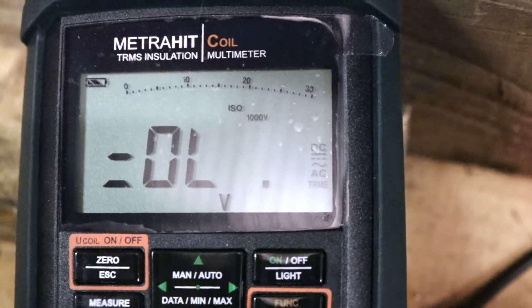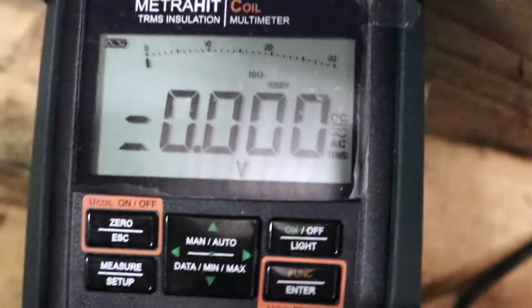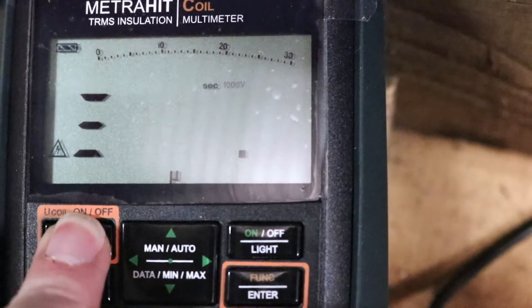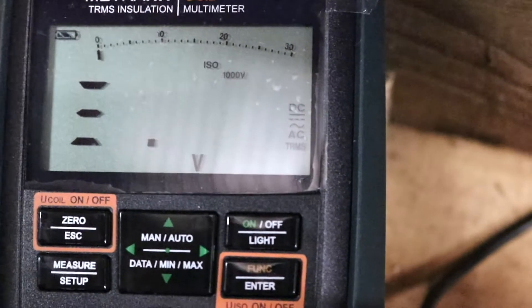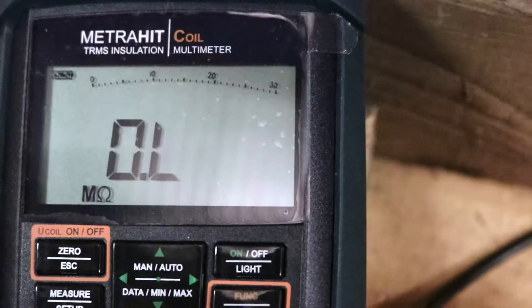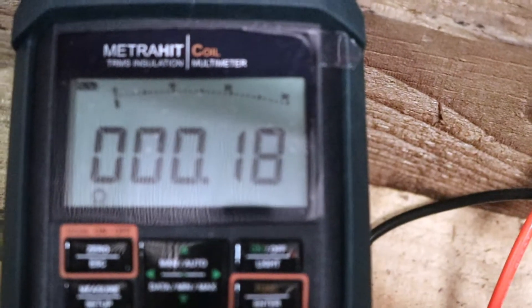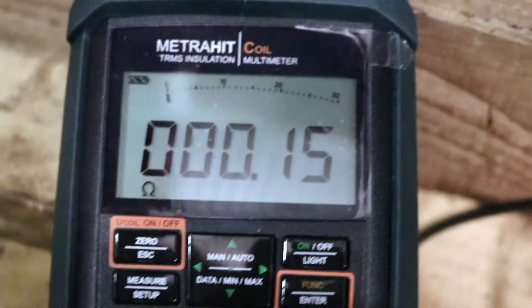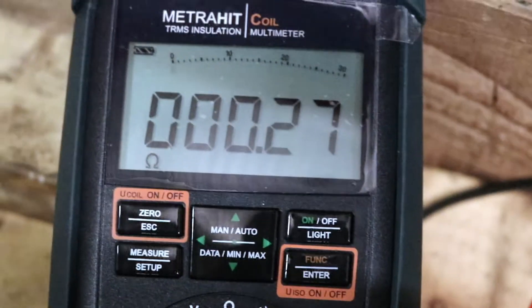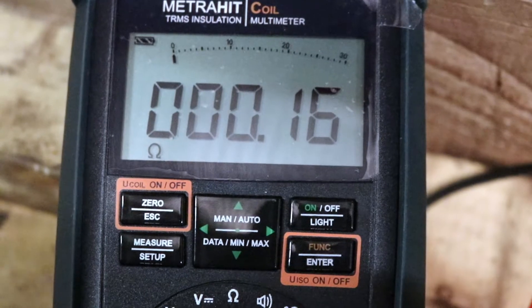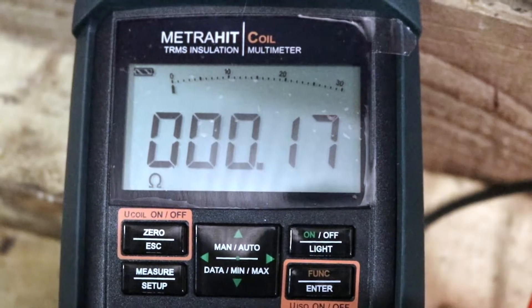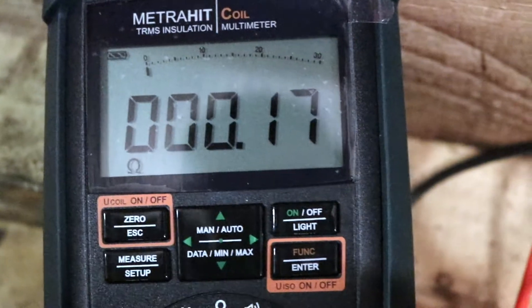So I'll go again. No reading at all. So if I switch it back to ohms and change the wire over. That's the ohm meter wired straight across. UW connection. And then UV connection. So the winding is there. The coil test doesn't work.